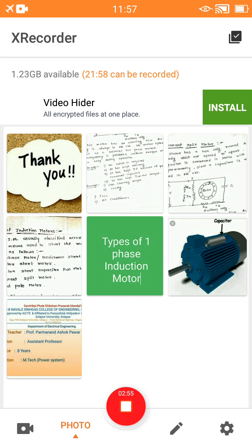The stator has two windings, the auxiliary winding and the main winding, which are spaced electrically 90 degrees apart from each other. The capacitor is connected in series with the auxiliary winding permanently, since the capacitor is always connected in the circuit.